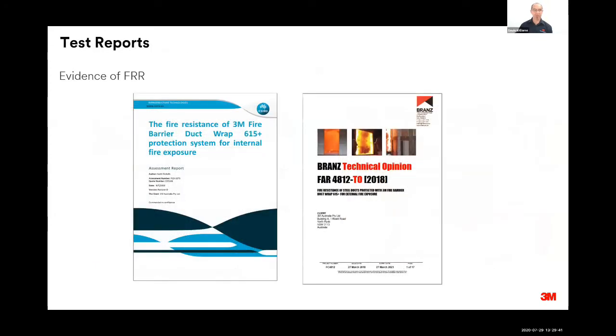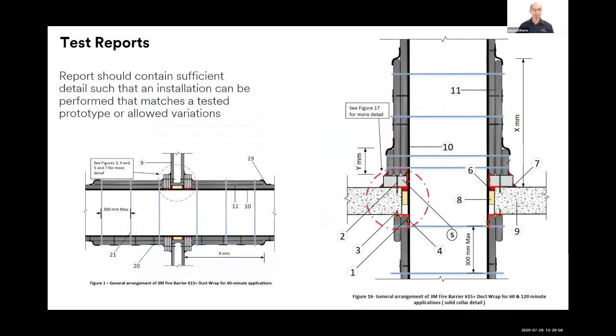And so the output for those tests is some test reports that give the evidence of the fire resistance rating and the configuration and the method of installing to achieve that and repeat that on site. So a test report should contain sufficient detail that installation can match the tested prototypes or the assessed and allowed variations from the test lab. So they've just got two pictures, one showing the horizontal duct going through a wall, and the other just showing the arrangement for a vertical duct penetrating a floor slab.